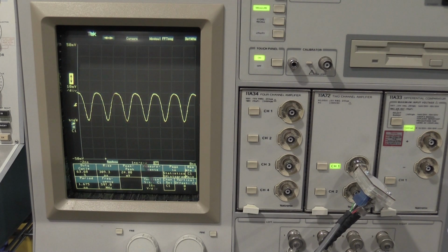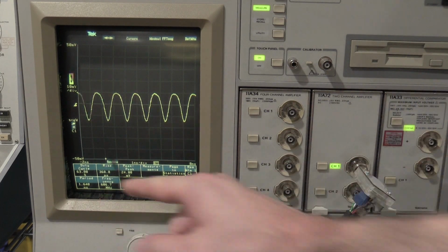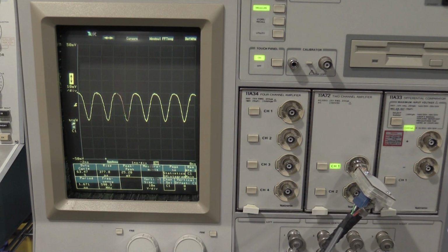I have a sneaking suspicion we're just not getting enough drive. The good news is the oscillator is running because my frequency is correct. We're right at about 600 megahertz. This is saying right at 600 megahertz, so the oscillator agrees with the front panel. That lets me know the resonant cavity is working, everything in the back of the cavity is working. I'm just not getting the drive level that I need because it's so low. Also, I'm turning up the front panel amplitude right now, and the signal's not changing. So I'm not getting enough drive out for the leveling head to do anything. This leads me to believe that we have a mostly functioning unit, albeit with some drive problems.